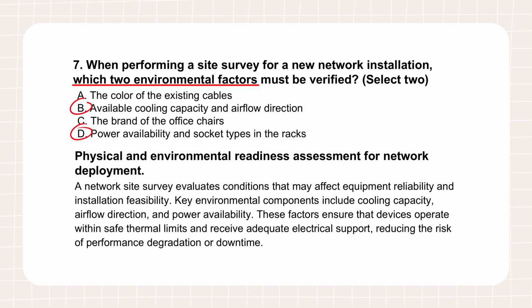And cooling is even more subtle, isn't it? It is. You might have enough total cooling for the room, but if your gear is fighting the airflow, sucking in hot air from another rack's exhaust, you create little pockets of heat. That just cooks the components over time - it kills them, reducing the lifespan of your expensive ASICs and optics. It's the difference between a smooth deployment and a 6-month delay waiting on an HVAC contractor. That's why it's 51% of the job.